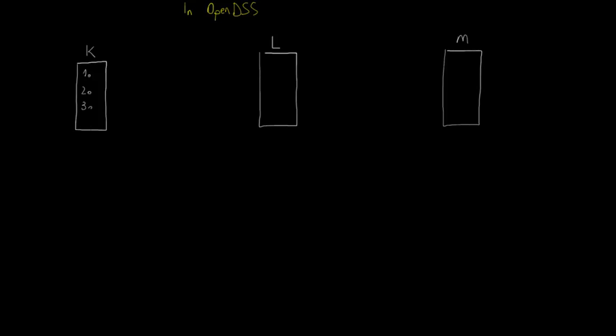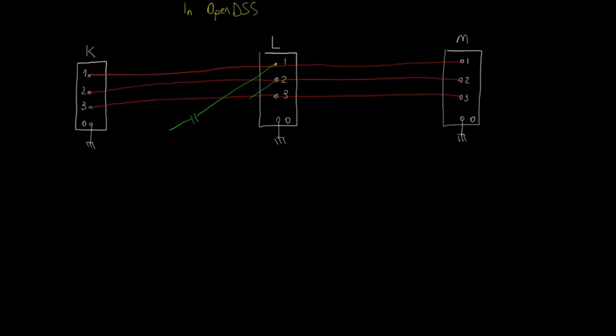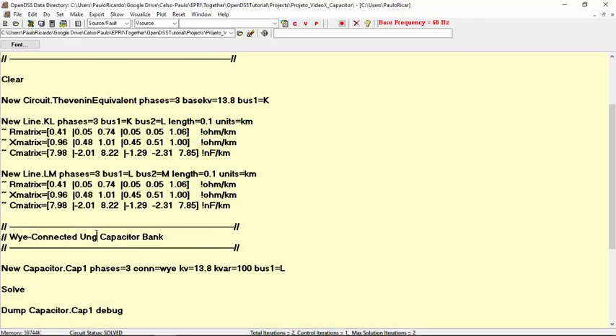In OpenDSS, we will have basically the same example. However, the capacitor bank's center node will be connected to node 4 of bus L, instead of node 0. Back to OpenDSS, I will change the name of the capacitor to CAP2, and now we have to clearly specify the bus2 parameter. We have the three branches of the capacitor bank connected to the same bus, bus L, and to the same node, node 4. Then, bus2 must be defined as L.4.4.4.